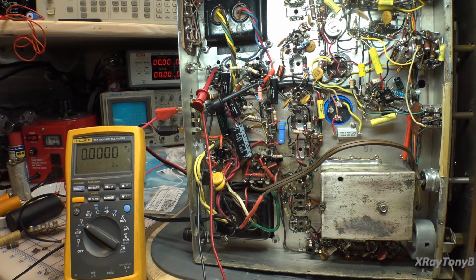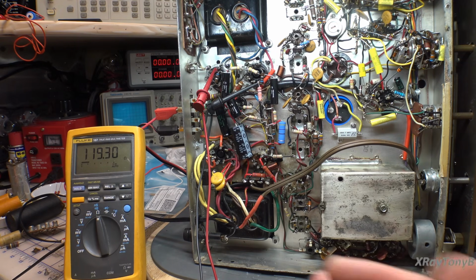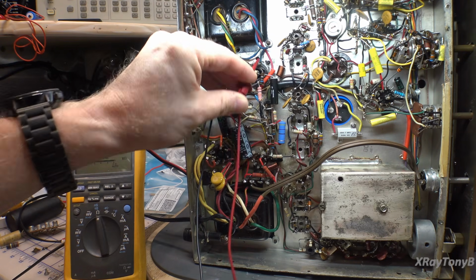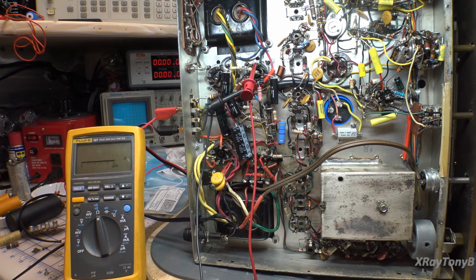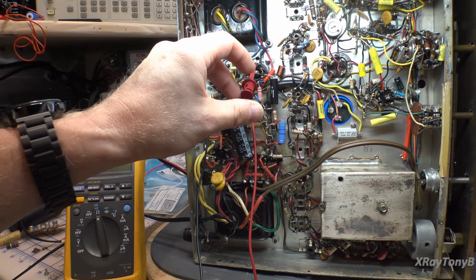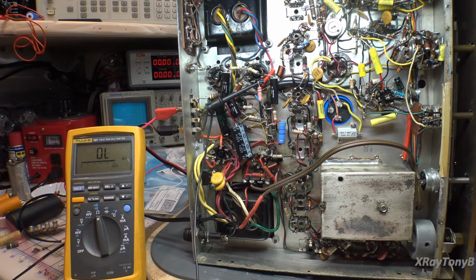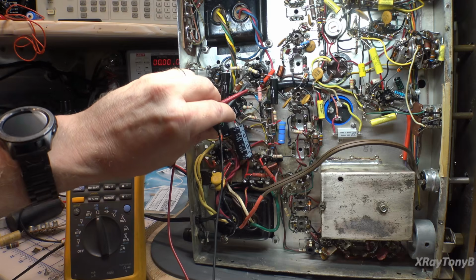So number one, if I go over to ohms and measure this first tube, it's reading about 119.3, bouncing around, so about 119 ohms. And if I look at the center tap to the other side, notice it's higher -- 147.6 or 7, and it'll change a little bit with the probes, but close enough. So we're going to write those numbers down.